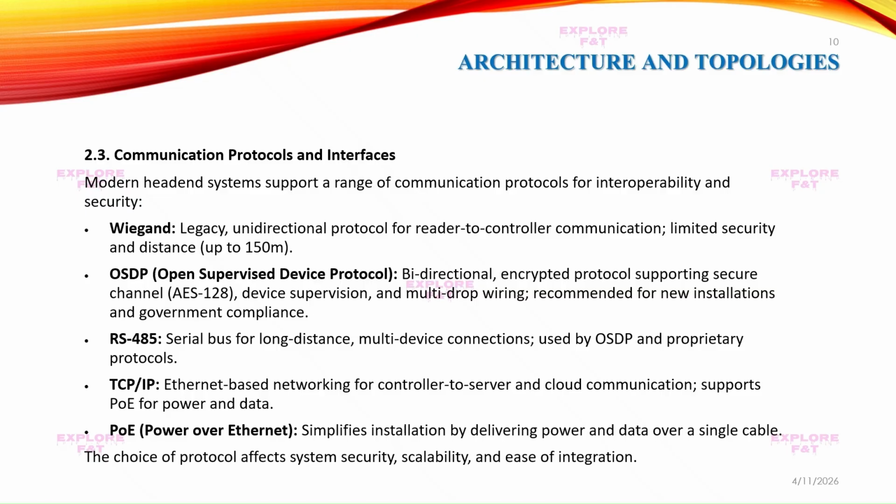So next one is communication protocol and interfaces. Modern head-end systems support a range of communication protocols for interoperability and security. First will be Wiegand. Wiegand is a legacy unidirectional protocol for reader to controller communication, with limited security and distance up to 150.